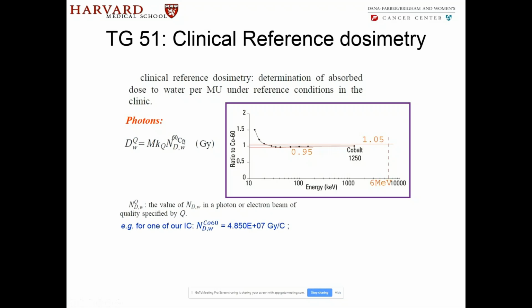In our ion chamber, for example, this is the number that we got for one of our ion chambers. What this number gives you is actually the amount of charge that you will gather. How much does that charge correspond to the dose? So you get that right away. What this means is per coulomb, it is 10 to the power 7 grays of dose will be delivered. That number is given to you by the lab.